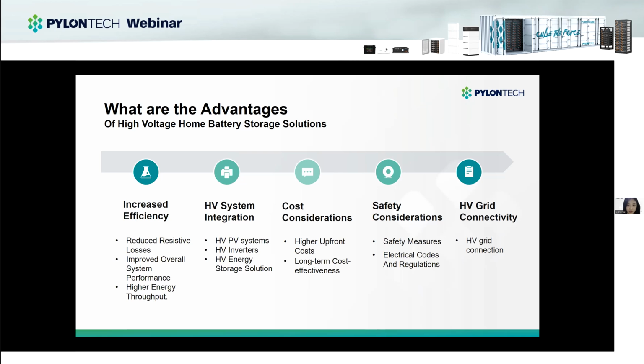The second advantage is system integration. If the customer already has a PV and a string inverter and wants to add an energy storage system, you may just add the batteries and the converter, serving it as an AC coupled system. So there is no need to replace it with a hybrid inverter. Then the cost considerations. The high voltage system allows users to use smaller cable sizes compared to the low voltage system. It would reduce the cost and the complexity of the installation, since thinner cables are easier to handle and require less space.